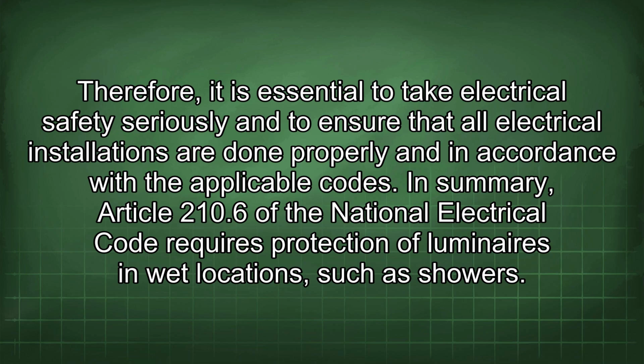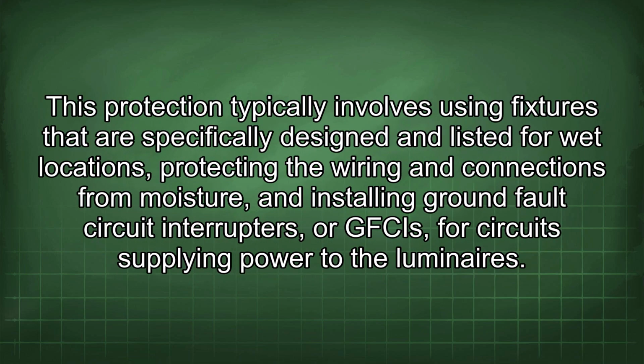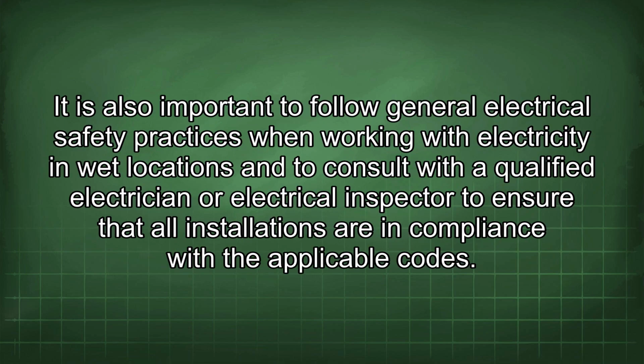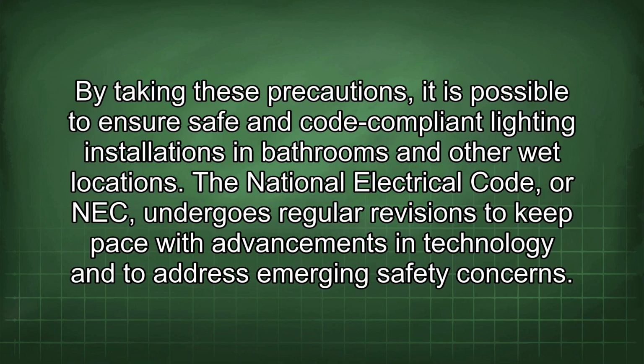In summary, Article 210.6 of the National Electrical Code requires protection of luminaires in wet locations, such as showers. This protection typically involves using fixtures that are specifically designed and listed for wet locations, protecting the wiring and connections from moisture, and installing ground fault circuit interrupters, or GFCIs, for circuits supplying power to the luminaires. It is also important to follow general electrical safety practices when working with electricity in wet locations and to consult with a qualified electrician or electrical inspector to ensure that all installations are in compliance with the applicable codes. By taking these precautions, it is possible to ensure safe and code-compliant lighting installations in bathrooms and other wet locations.